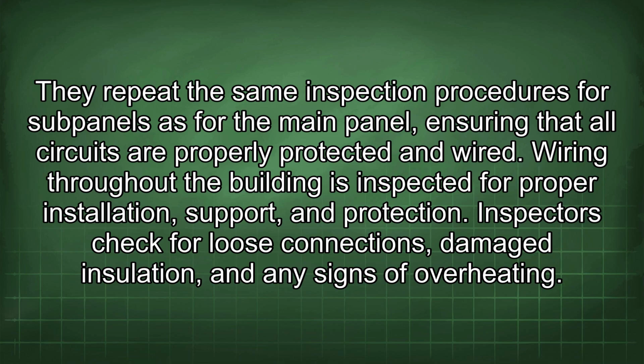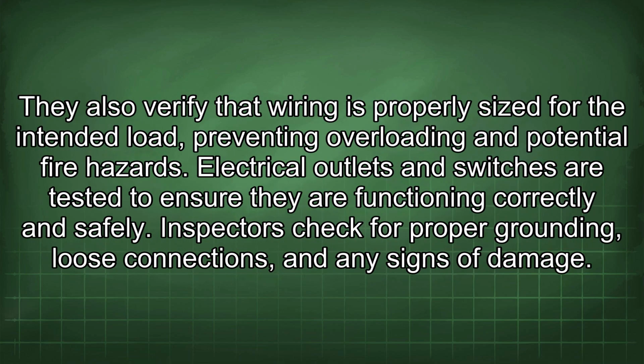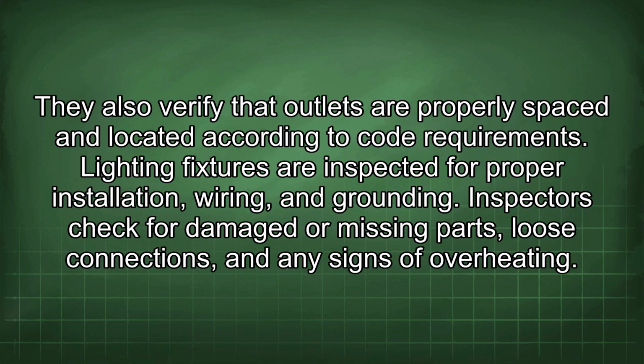Inspectors check for loose connections, damaged insulation, and any signs of overheating. They also verify that wiring is properly sized for the intended load, preventing overloading and potential fire hazards. Electrical outlets and switches are tested to ensure they are functioning correctly and safely. Inspectors check for proper grounding, loose connections, and any signs of damage. They also verify that outlets are properly spaced and located according to code requirements.